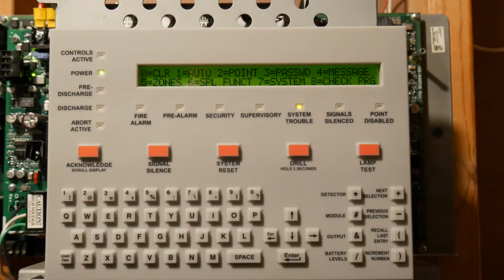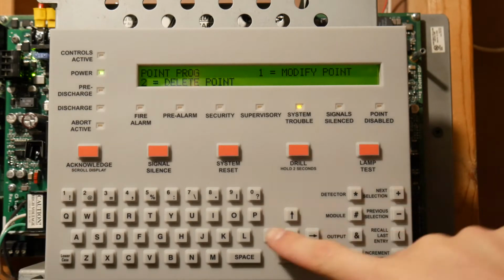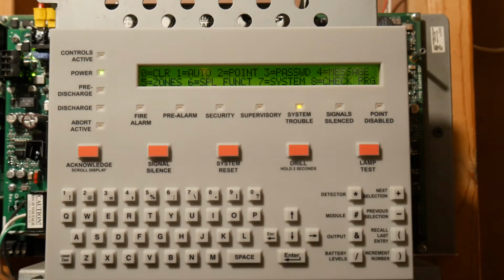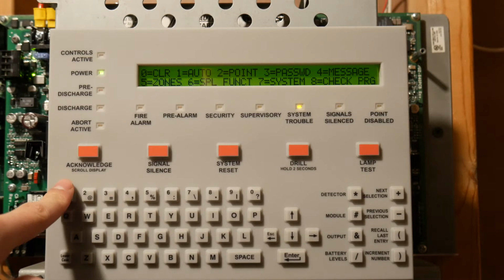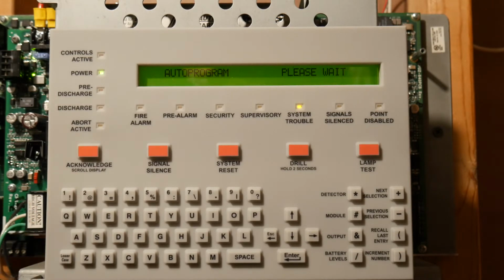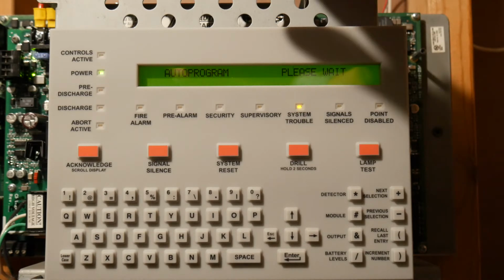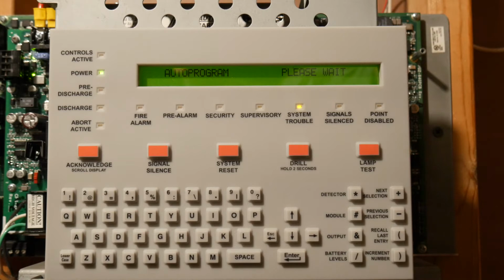And how do you add points? Well, you cannot go into points because you cannot add individual points. You have to do auto programming. So you're going to press auto program and it's going to search the SLC for points. This takes like 2 minutes. It's probably because of how old this panel is and also how many points the panel could support, so it's probably a mix of both. After it's done auto programming, I'll cut back to that.